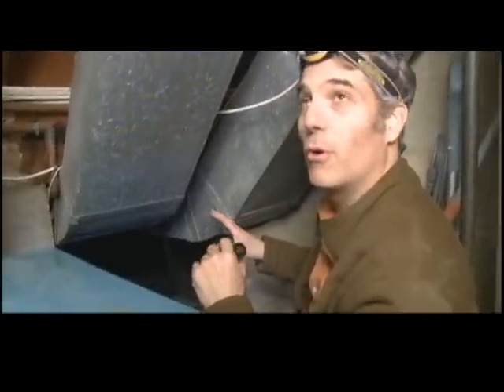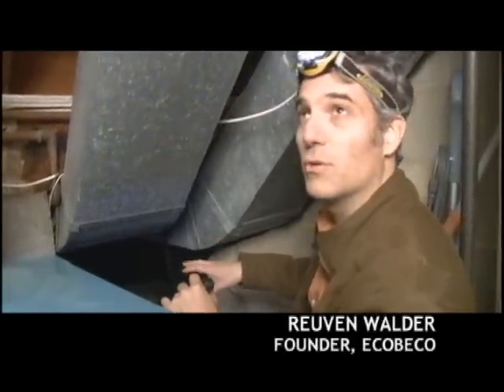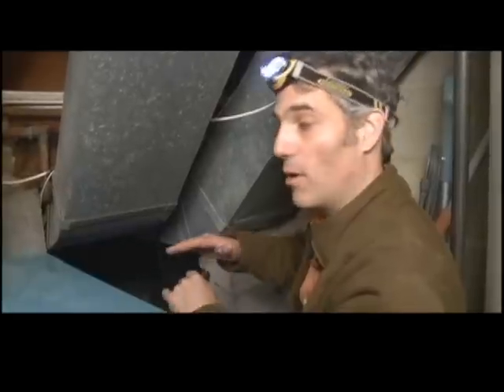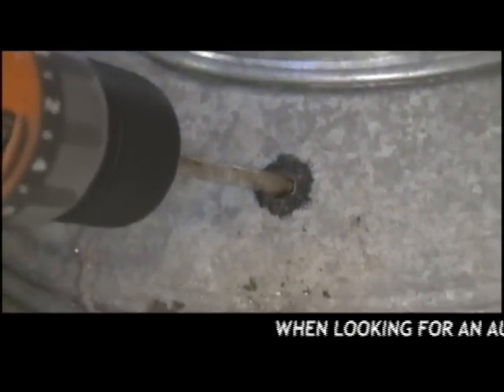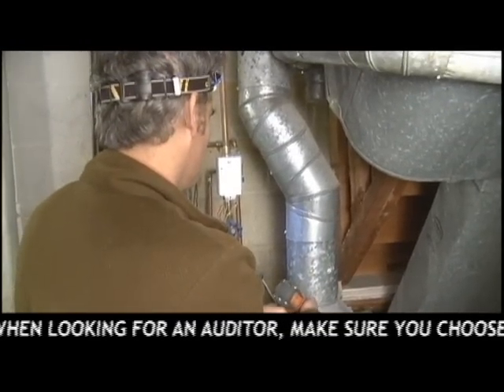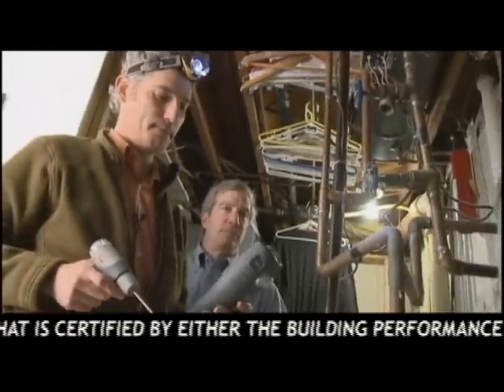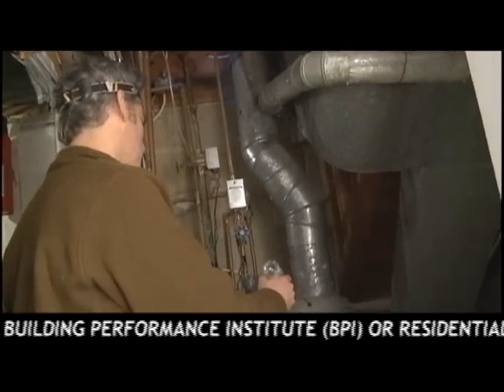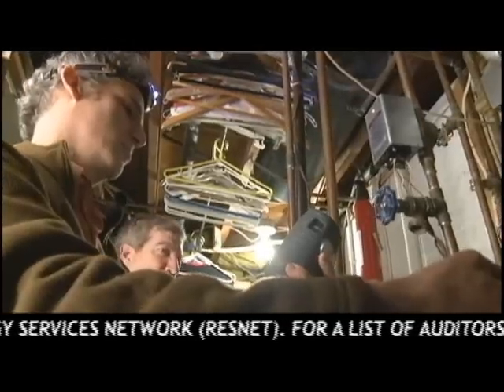Joe, there are a couple of important things to consider here in a crawl space like this down in the basement — we want to make sure that there's no moisture infiltrating into the house from here. There is a vapor barrier in here, really a sheet of plastic, but it's not been spread out to cover all of the soil down here. That's absolutely critical, that we make sure there's a secure vapor barrier down here. We'll also look at safety components — we want to make sure there are no indoor air quality concerns before we go ahead and air seal it, and most importantly, carbon monoxide exhaust gas concerns from an oven, furnace, or water heater.